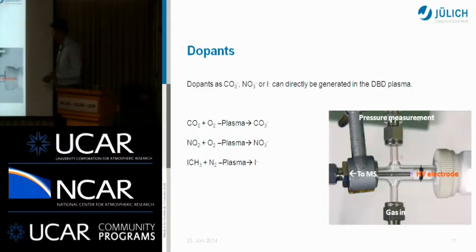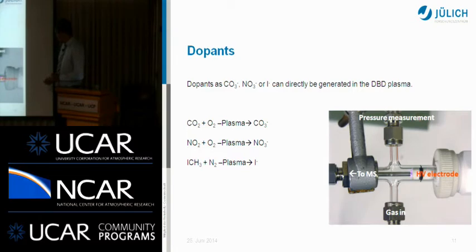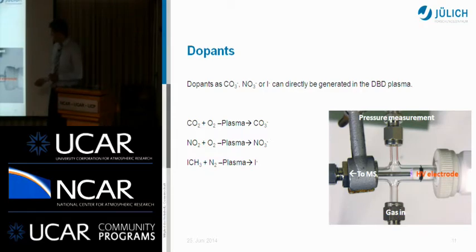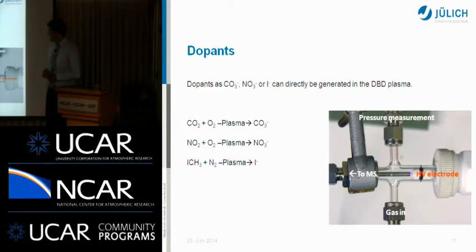This is our plasma — you can see the plasma burning. Here you have the high-voltage electrode coated with a dielectric, and you have the opposite electrode, which is a stainless steel capillary that samples the ions directly into the transfer stage. You have additional ports for pressure measurement and the gas inlet, and thereby you can control the properties of your plasma ion source.